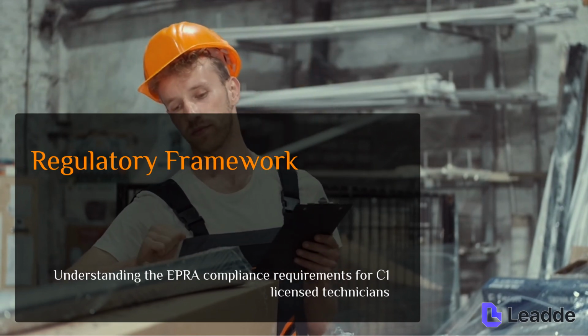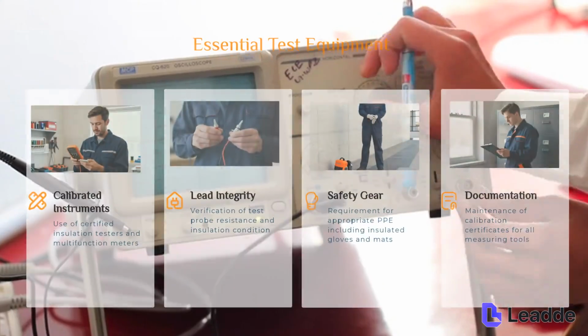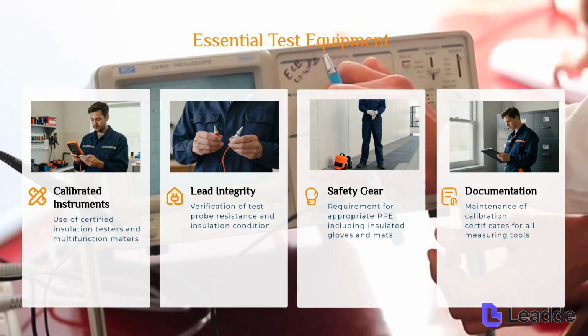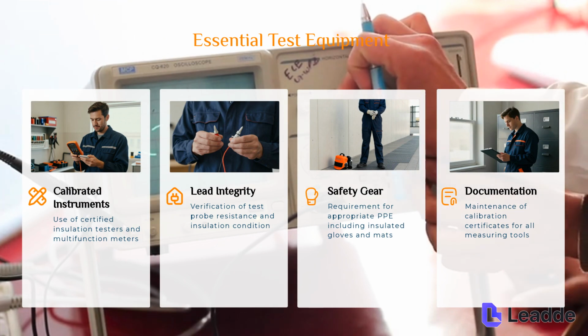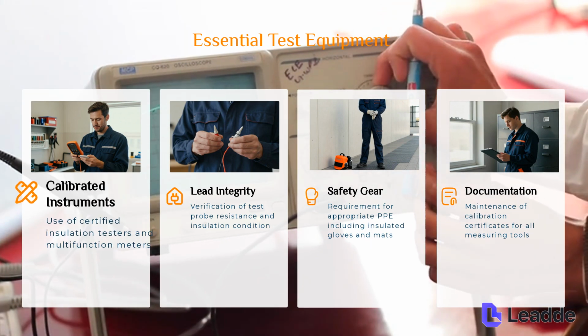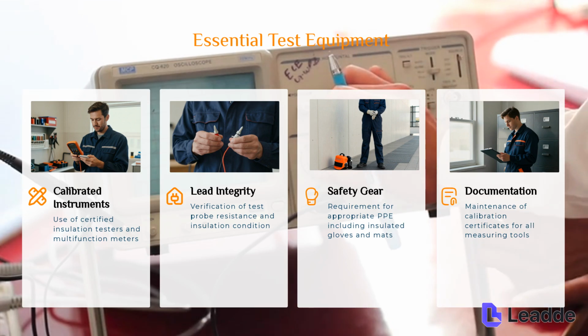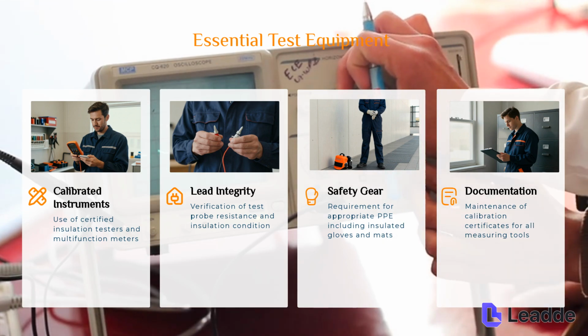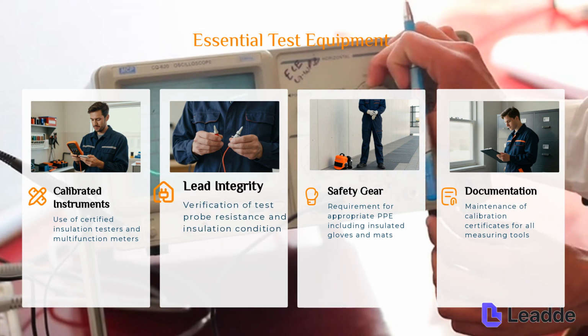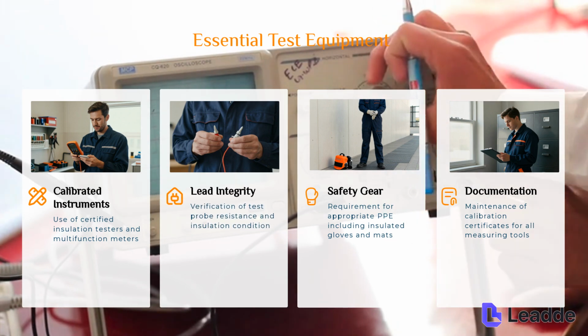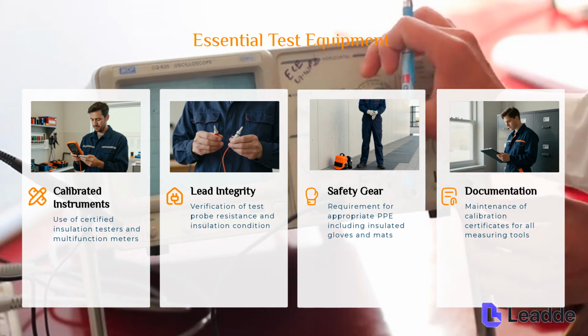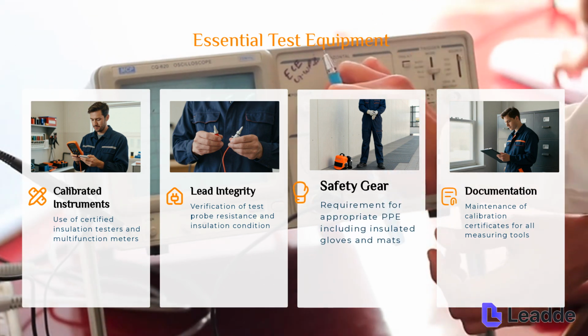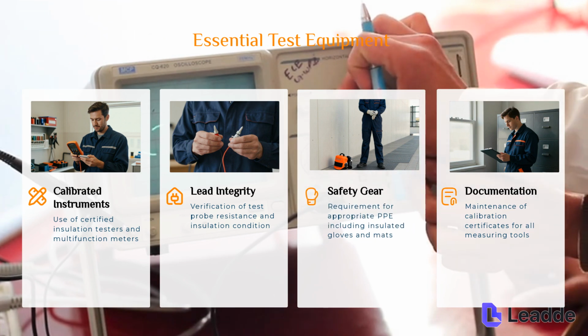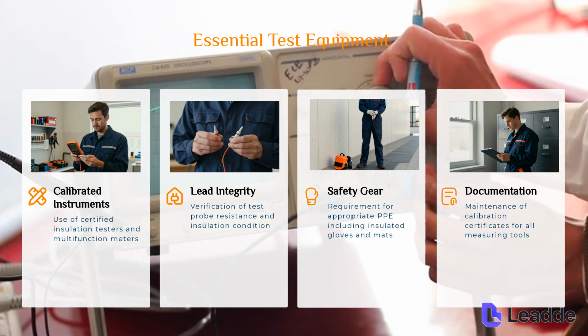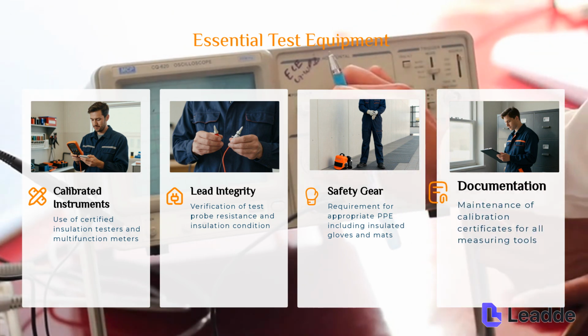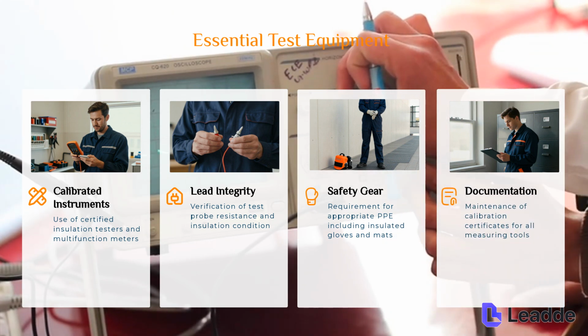Let's discuss the essential test equipment. First, all operations must use calibrated instruments, including certified insulation testers and multifunction meters. Second, the integrity of testing leads is critical. This involves verifying test probe resistance and the condition of their insulation. Third, appropriate personal protective equipment, such as insulated gloves and mats, is mandatory. Finally, it is imperative to maintain complete documentation, including calibration certificates for all measuring tools.